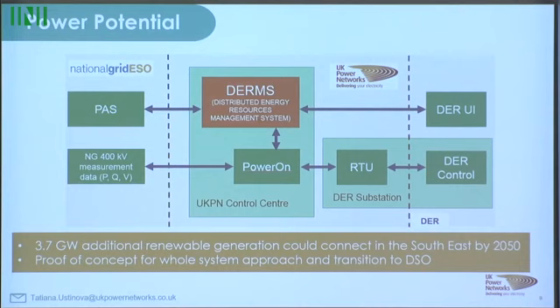Day ahead in this trial, the DER would put in their volume and price, bidding for an availability and utilization period, and send it to us. We run a flow model to assess if there's any constraint on the network with what they're bidding, and whether there'd be any problems if we accept the tender. We then pass this information to National Grid, who run their assessment and tell us what they want and don't want, and then we dispatch automatically from the DER side of the substation.